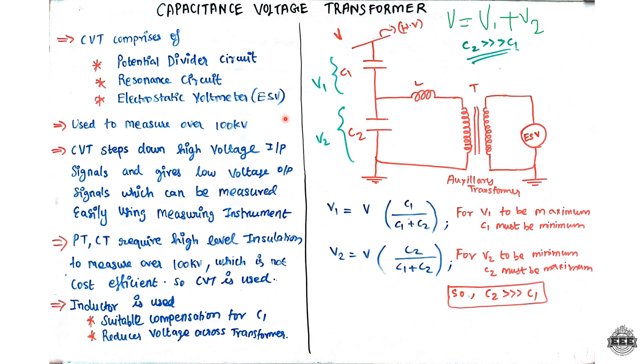For high voltage measurement using current transformers and potential transformers, the main reason they are not preferred is that CT and PT require high voltage withstand insulation at 100KV levels. If the insulation is damaged, the cost of total loss is very high. So for 100KV applications, CVTs are used instead, as the cost is more feasible.